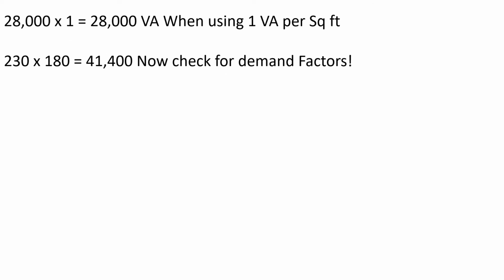Let's go ahead and multiply our square footage. We have 28,000 square feet multiplied by 1 VA per square foot. That's going to give us 28,000. Now let's take our receptacles. We have 230 multiplied by 180. That is going to give us 41,400. Now, every time you get your total load, you have to check for demand factors. Yes, in this case, the demand factors in 220.44 do apply.